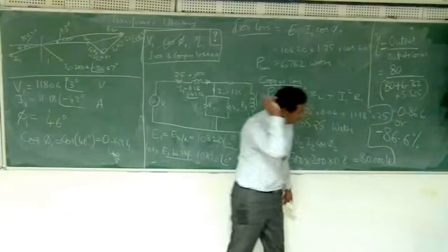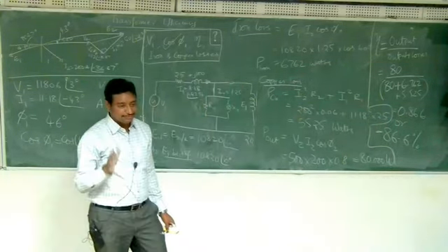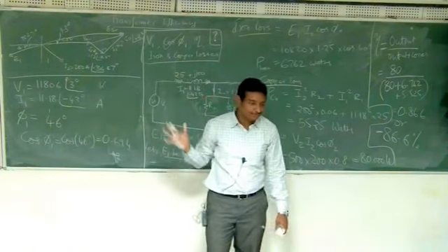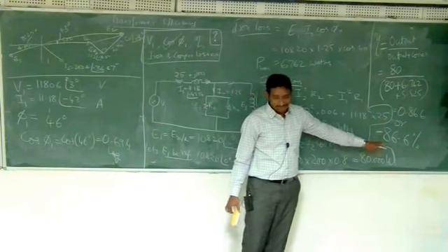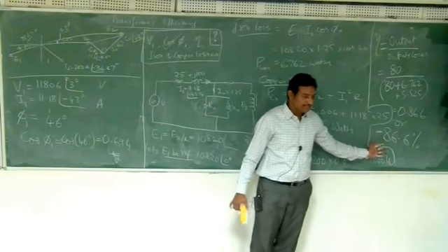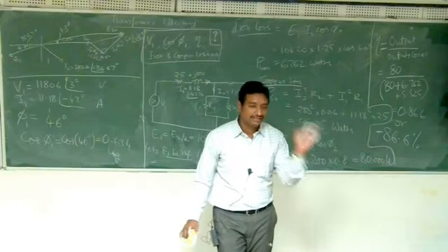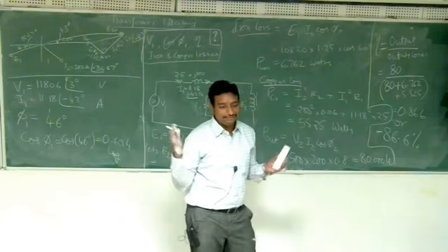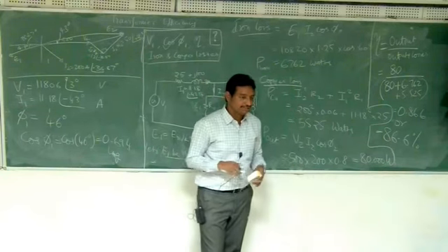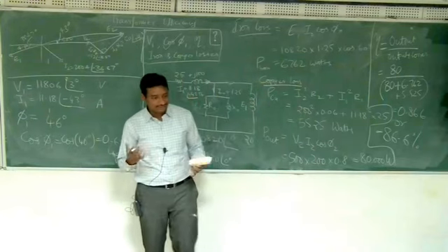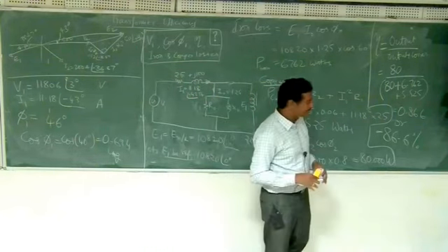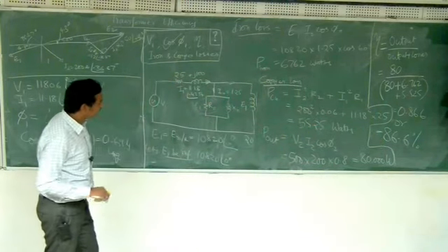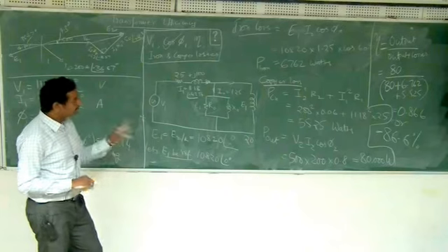That's my efficiency. Typically efficiency should be 95%, but because of the constants chosen for this problem, it is coming out less. I hope the calculations are correct. So it is 86.6%. Any typical transformer you will find definitely above 90% efficiency, 95%. And very, very large transformers even touch 98, 99%. Very efficient, with proper design. But anyway, for our problem, we got this answer. So that is about efficiency.